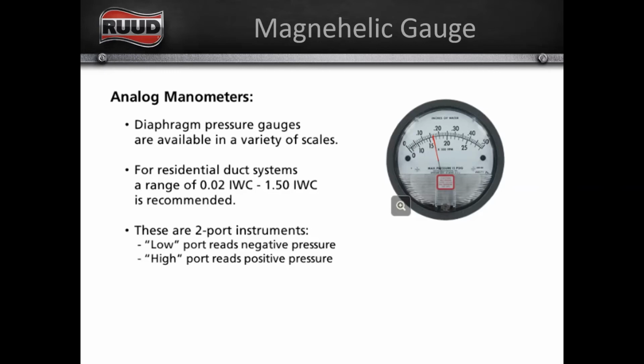Many out there have static pressure that far exceeds, or is much higher than, a half inch static. So the magnehelic gauge has a low port and a high port, right? Low port is for the negative pressure. The high port is for the positive pressure. You can measure them both at the same time and it will calculate it. You can measure one or the other. And typically it's good to do all of those: measure your total external static, then measure your supply, then measure your return, or any combination of those. So you can see exactly what's happening with your return and your supply.